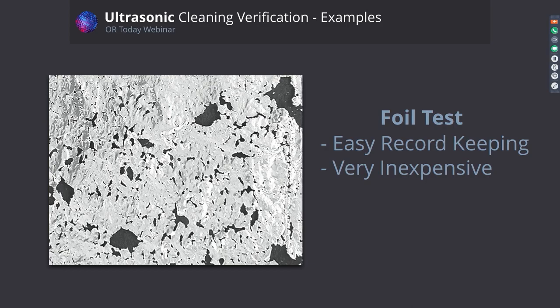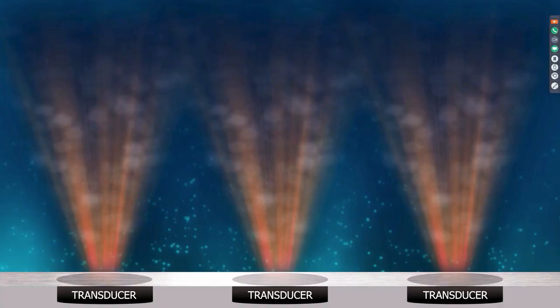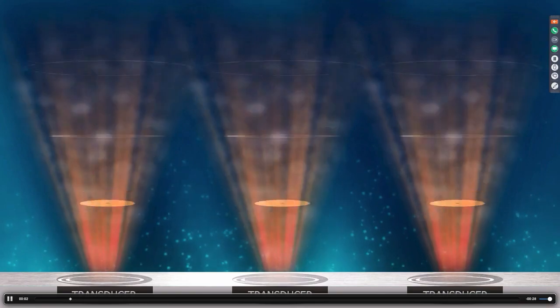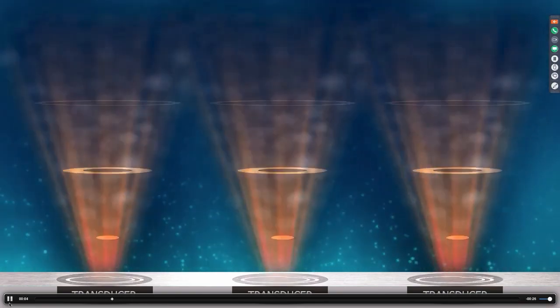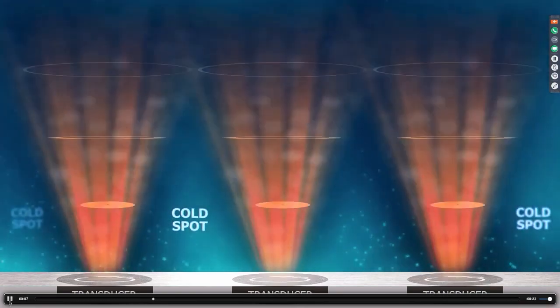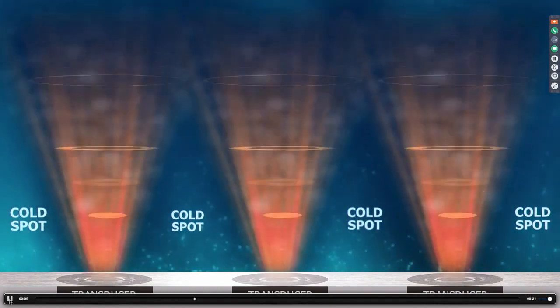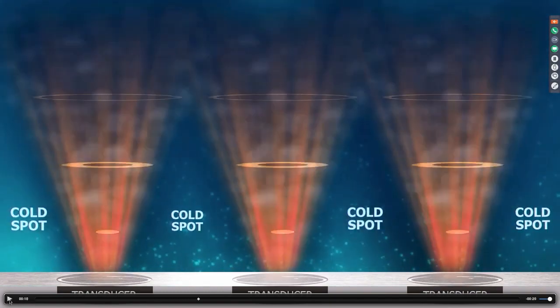So with regards to also cleaning verification, when we're talking about in a specific case with bonded transducers, where the transducers, those speakers, are glued to the underside, you can see the cavitation energy spiking up from the bottom through the basin. Now, between these devices, between these transducers, you can have cold spots. Now, this is showing you just very clearly where these cold spots might occur, where the cavitation energy doesn't cross over.